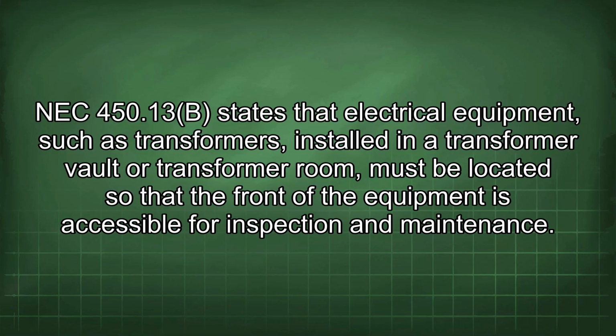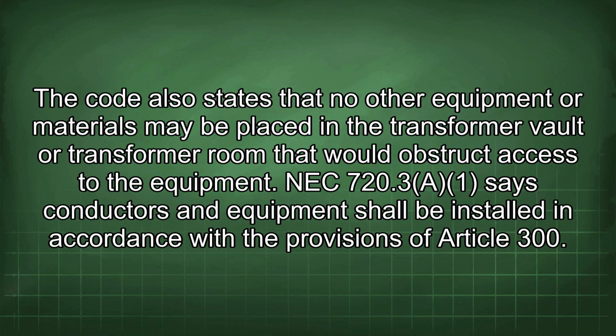NEC 450.13b states that electrical equipment, such as transformers, installed in a transformer vault or transformer room, must be located so that the front of the equipment is accessible for inspection and maintenance. The code also states that no other equipment or materials may be placed in the transformer vault or transformer room that would obstruct access to the equipment.